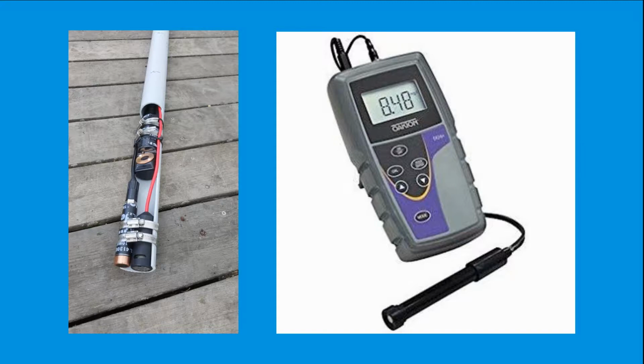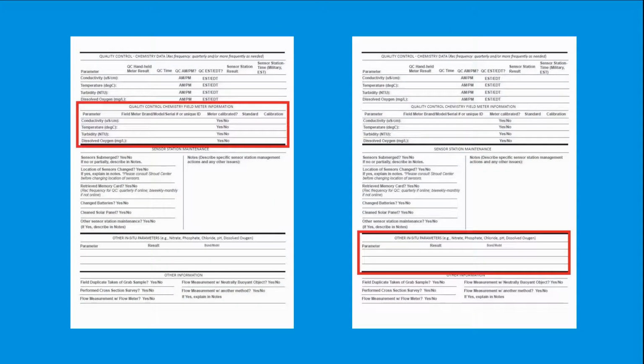If there are other probes attached to the sensor station besides turbidity, conductivity, depth, and temperature, you should consider purchasing instruments to QC those as well for a full data quality check. Just as a reminder, be sure to record the name of the meter and the calibration result of each instrument onto the field visit data sheet under the Quality Control Chemistry Field Information section.